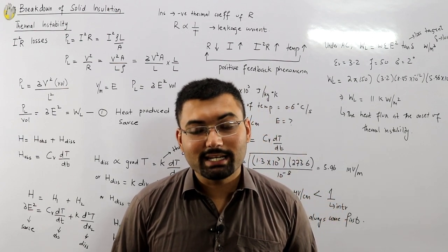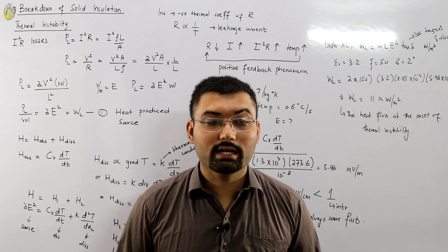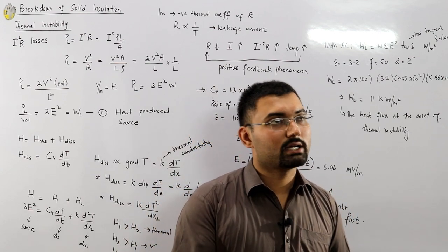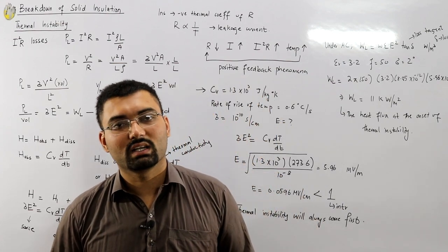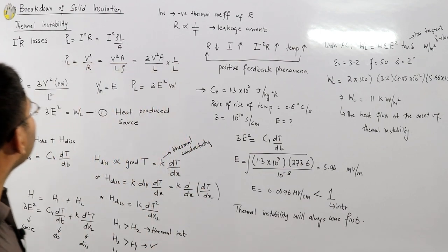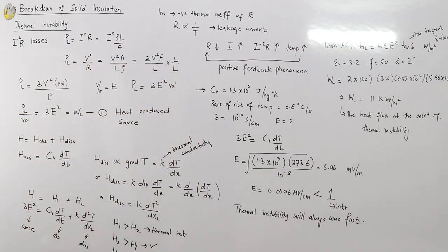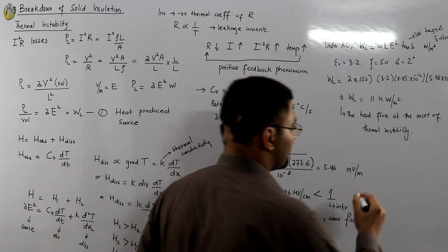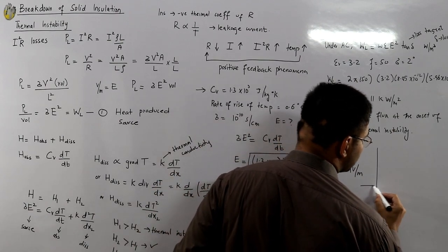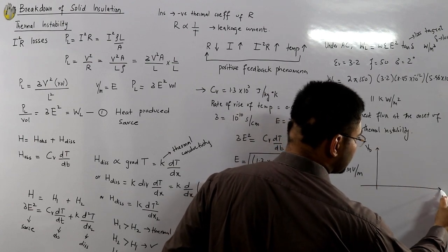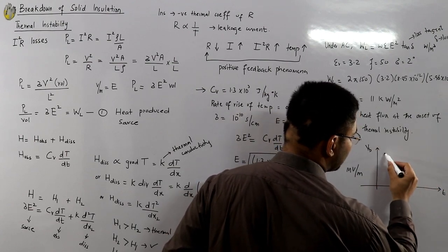For circuit breakers, we need an insulation whose dielectric strength is recoverable, because we have a number of trippings in a day. How much time you operate your circuit breaker, right? So I believe that you've got the main idea of the thermal instability. Temperature increases, resistance decreases for an insulation. But this takes time. As we saw in the breakdown voltage versus time, this takes time.